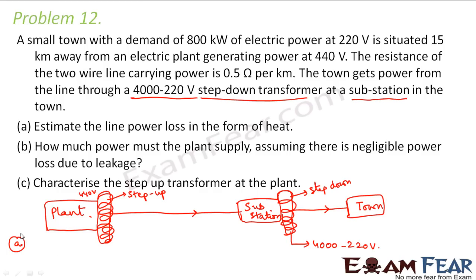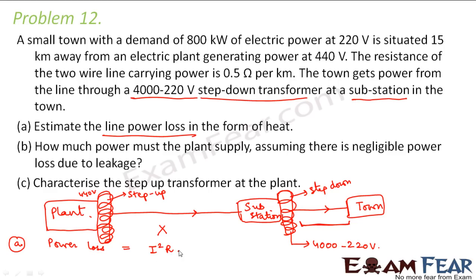In the first part of the problem we have to calculate the line power loss in the form of heat. There will be no considerable line power loss from plant to the substation, because the step-up transformer increases the voltage and decreases the current significantly. So the line power loss is only involved from the substation to the town. The power loss is given by I²R — the total resistance of the wires from substation to town multiplied by the square of the current transferred.